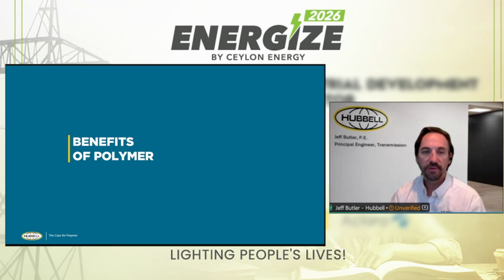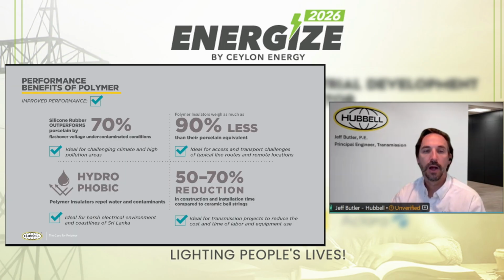So now let's talk a little bit about the benefits of polymer in general. When we're looking at the use of polymer insulators versus ceramic insulators, porcelain or glass, I've alluded to it a little bit, but one of the key characteristics, as I mentioned, is that hydrophobicity, which is very effective in contaminated environments. So we saw a 70% better performance than ceramic insulators when it came to flashover voltages in a contaminated environment. There's also tremendous weight savings, up to 90% less than a porcelain or glass equivalent string, which is ideal for access and transportation, for handling. Typically, transmission line routes are in remote locations. Access can be challenging, so reducing weight, reducing transportation costs, reducing handling is very advantageous for many of these projects.